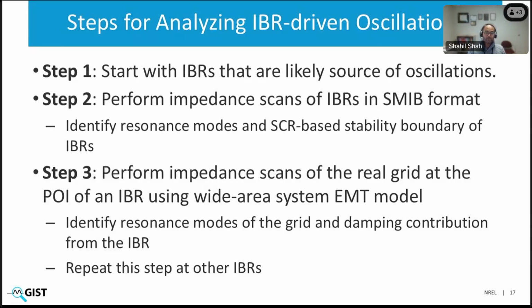Once we do that, we go to step 3, where we obtain the impedance response of the wide area grid using the wide area EMT model. The grid impedance response is obtained from the POI of a particular IBR for different dispatch conditions within the grid. Those are basically giving you the puzzle pieces that represent the grid. And now you can mix and match and understand how this particular IBR that we have selected is impacting the stability of the grid, impacting the damping of certain oscillation modes. And then we repeat the steps at other IBRs.